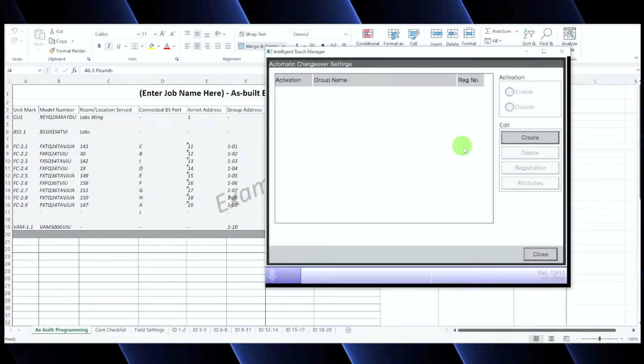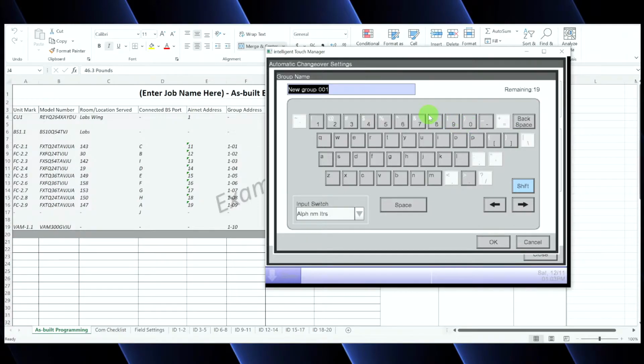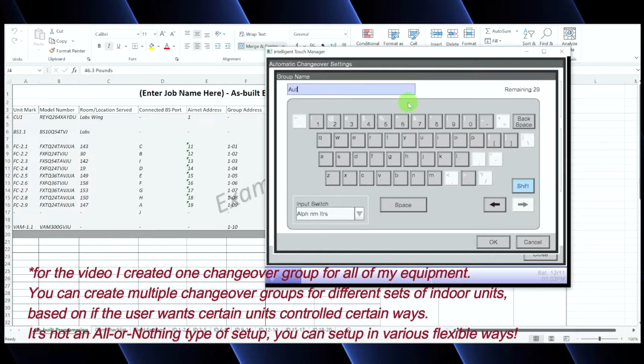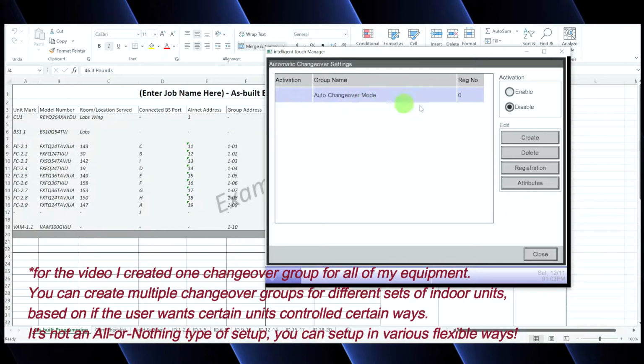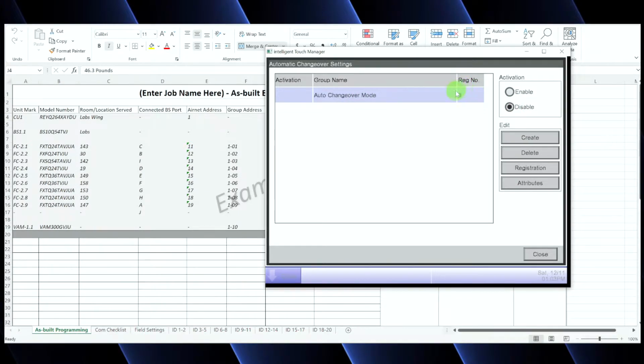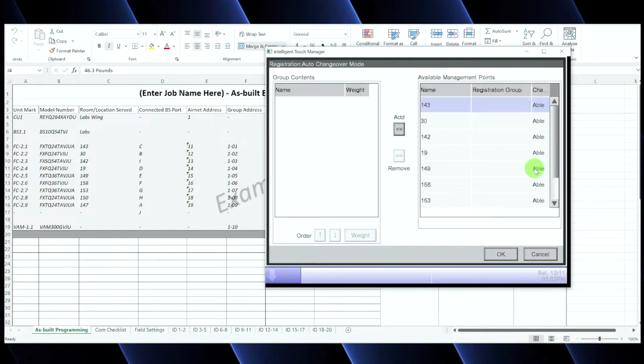So back on the ITM, we're going to go ahead and create a new auto changeover group. What I'll typically call this is the auto changeover mode. You can call it whatever you want. Once you create it, it's going to be disabled by default, and that's fine. But what we need to do is register our indoor units to this mode. So we go over to the right-hand side, we click on register, and all of your indoor units are going to be shown as available management points.